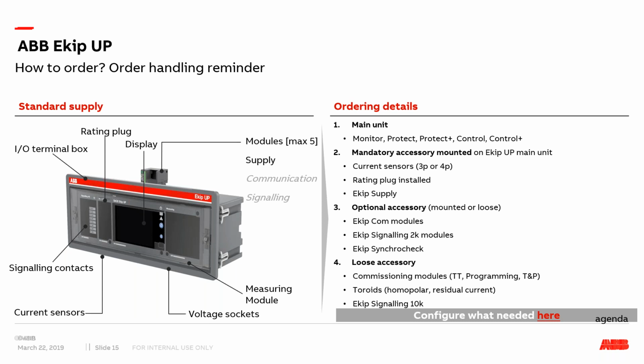Once you've chosen that, you need to decide on the number of phases you're trying to work with, whether monitoring, protecting, or controlling across 3 or 4 phases. Then you can choose the number of phases and the current sensor type, meaning the type of CTs you're looking for.